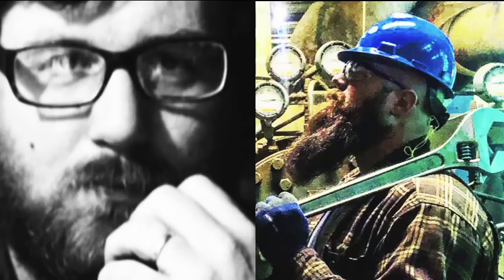You mentioned the other day that you're the most happiest in a mechanical room. How much time do you spend out of the mechanical room on those individual fan coils, fixing water leaks, etc.? Do you spend more time with those or more time right at the source? I probably spend more time in a mechanical room or on a roof. Sometimes I end up in the building doing stuff at the end. For our branch and what I do and who I work for, typically I work on the source of the chilled water or cold air, whether that's the big air handler for the building or the chiller itself.